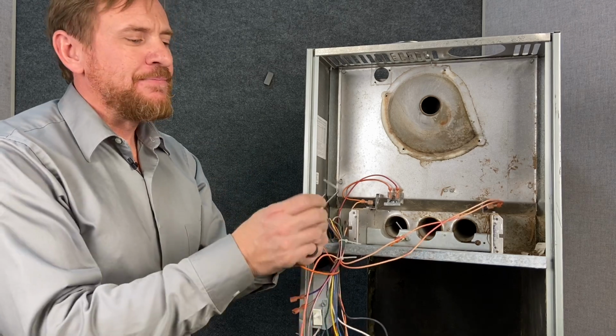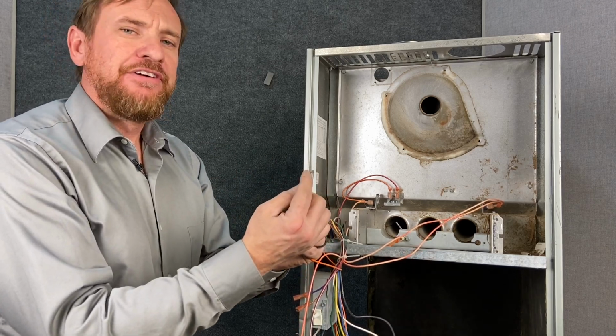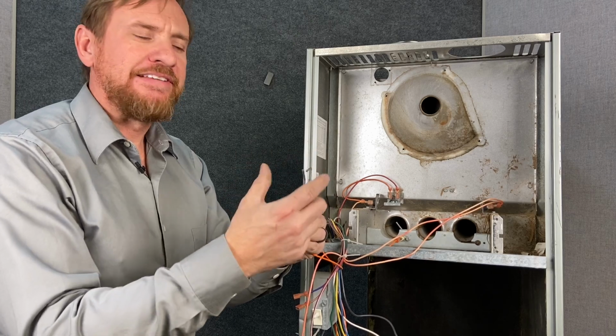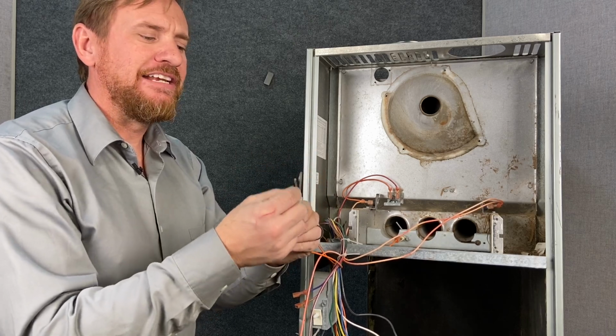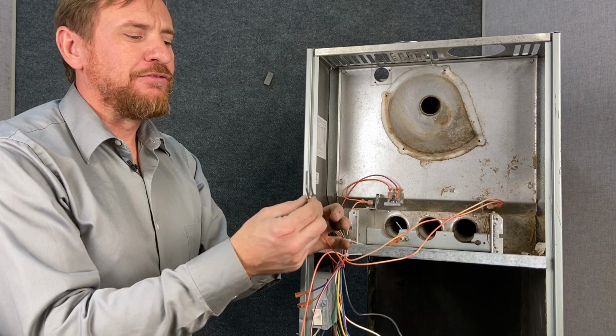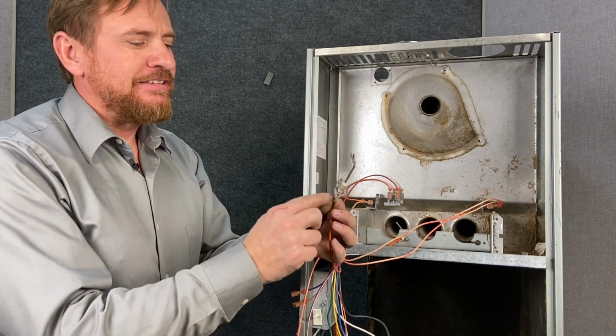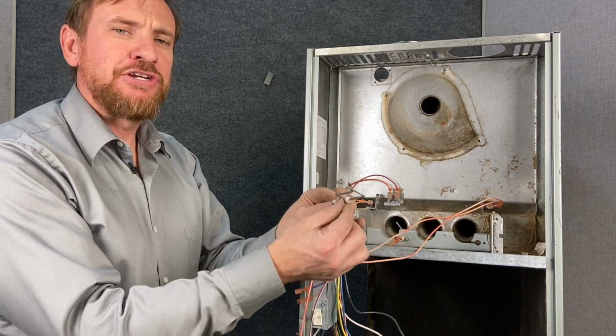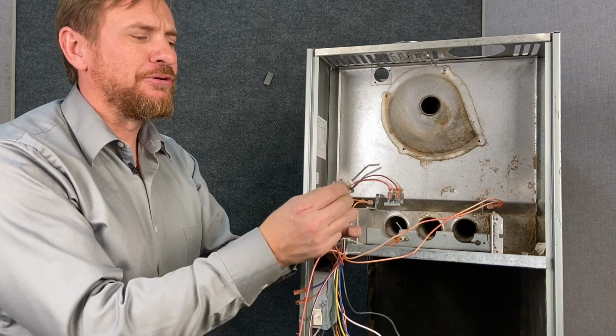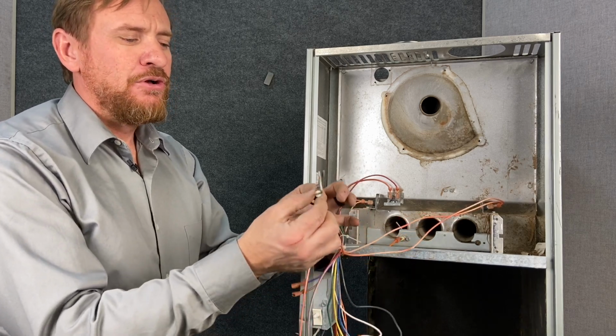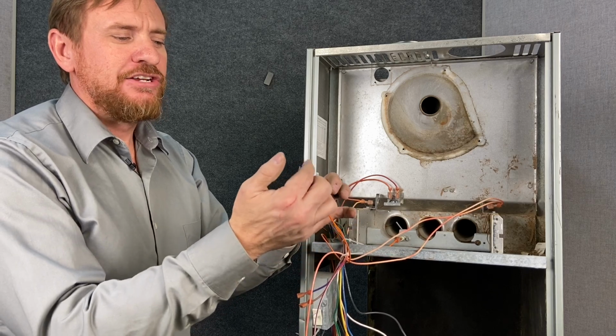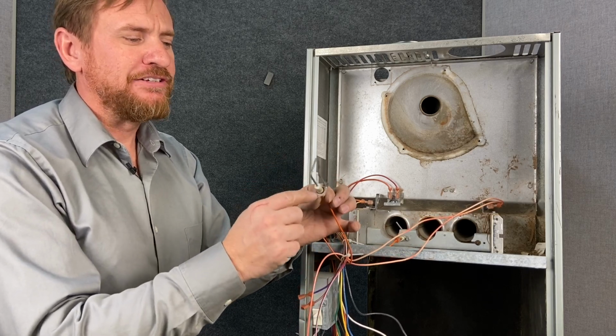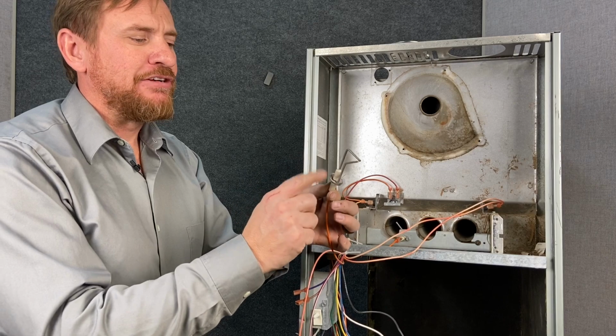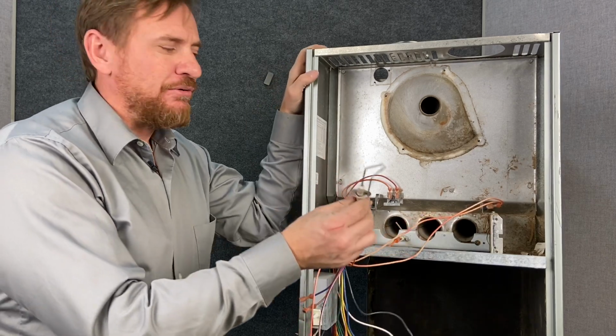The silicone gets heated up by the flames and it really leaves a glass coating and it doesn't allow it to arc correctly. The gap between these two is also very important. You want to make sure that you don't spread these out or get them too close together. So when you're cleaning these, you want to be mindful not to bend these forward or backwards. When I'm inspecting this, I really just want to inspect the porcelain to make sure this porcelain doesn't get cracked or brittle or broken. Other than that, it's very simple. One wire comes up to this and it just arcs across the two. So make sure they're grounded good, make sure they're cleaned good, make sure there's not a crack in that porcelain, and you're really good to go.